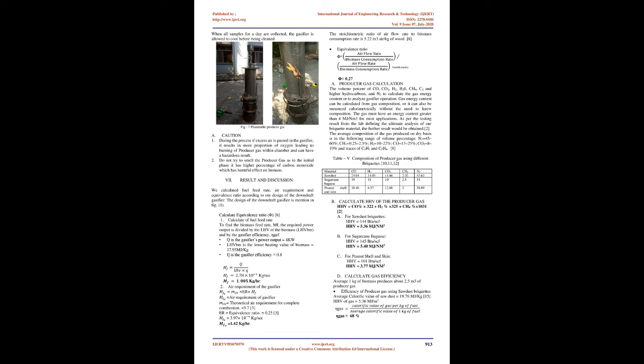Procedure to Perform on Gasifier - Caution: Pre-fill the hearth of the gasifier with charcoal; the primary aim is to fill the bottom of the reactor as well as the reduction bell with charcoal. Before starting the gasifier, the top port needs to be sealed. The ash/startup port should be left open. This makes it easier to use lighting fluid in the bottom close to the grid section for preheating the coal. Recheck that all caps and plugs are in place. There should be no place for air to leak into the gasifier. Miscellaneous operations like installing the data logger, virtual instrument, and placement of thermocouple in the gasifier need to be ensured. According to theoretical data, the airflow and fuel feed are maintained simultaneously once the coal achieves red-hot condition.